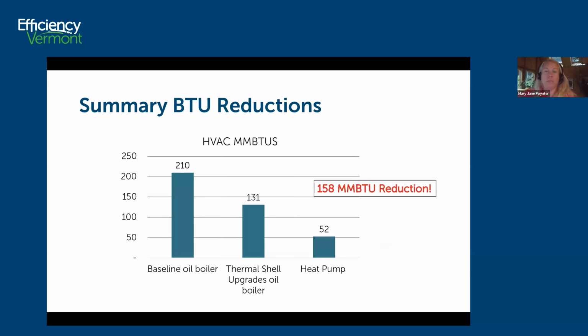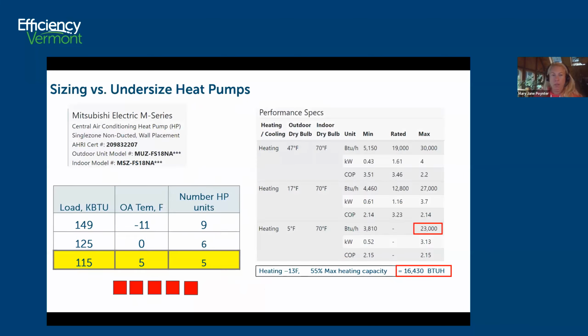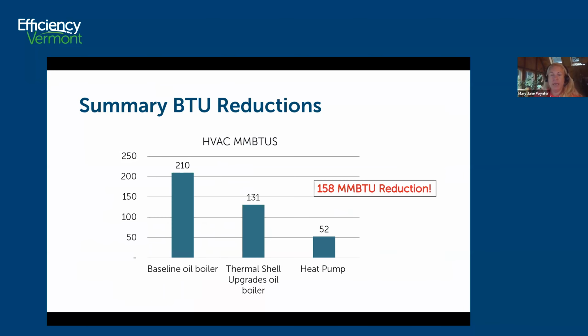Just a summary of the BTU reductions, and then we'll look at the paybacks. So we started with 210, and then we did the thermal shell upgrades. We went to 131, and then we looked at the heat pumps, and it comes down to 52. So the thing to remember is that with heat pumps with their COP of 2.5, now your installed capacity is significantly less because of the COP.